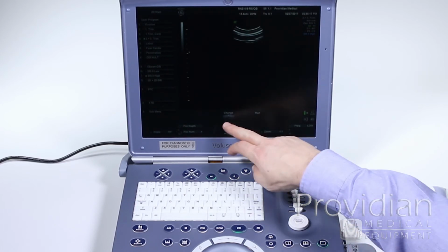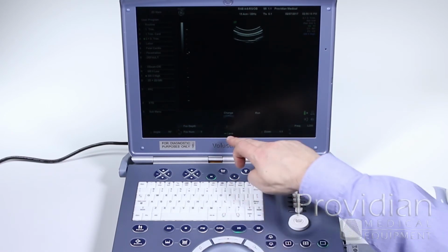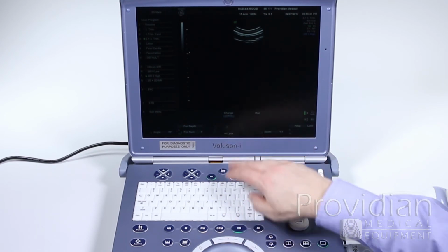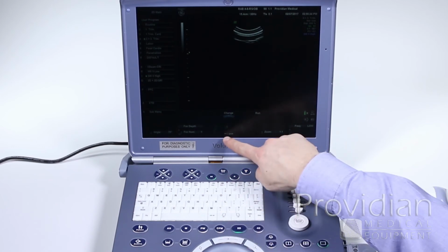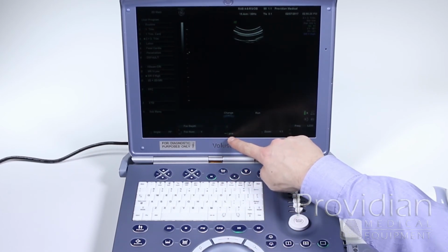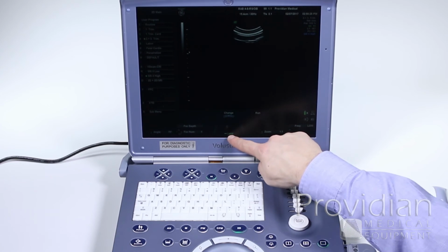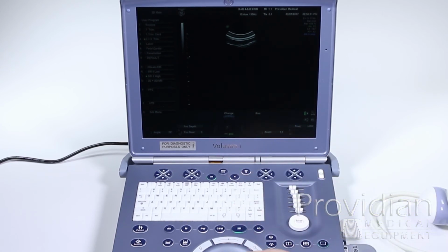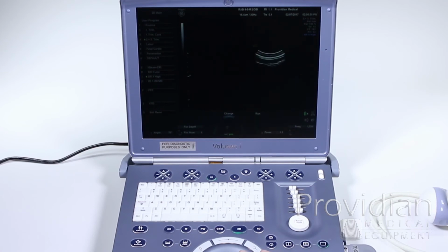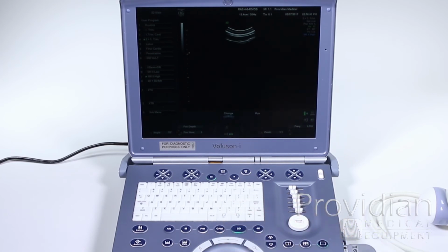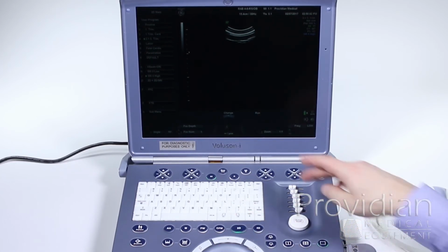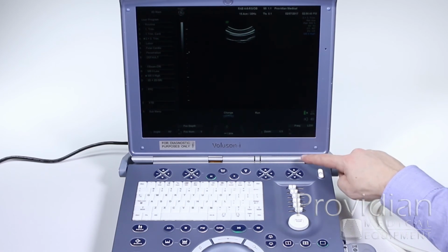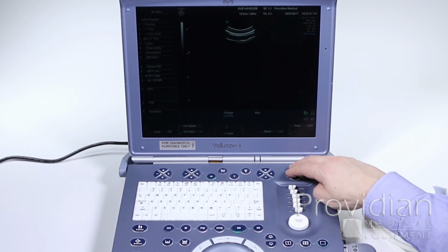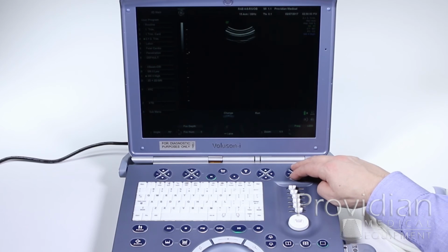Here, we talked about this key up here. It says change. So this is saying what's going to happen with the trackball right now. So it's saying 3 dots, meaning the trackball won't do anything. If I click this to change, now green is highlighted for position, and this is just going to change the position of the probe on the screen if I want to move that around. Then I can hit it again to make sure that I don't make any more changes. Zoom to zoom the image greater, and you have your frequency. You can increase this, since it's on harmonics, you can go high and low.